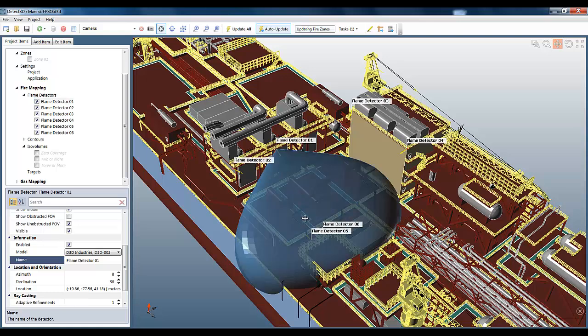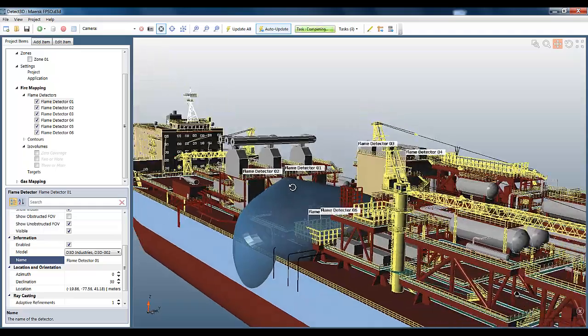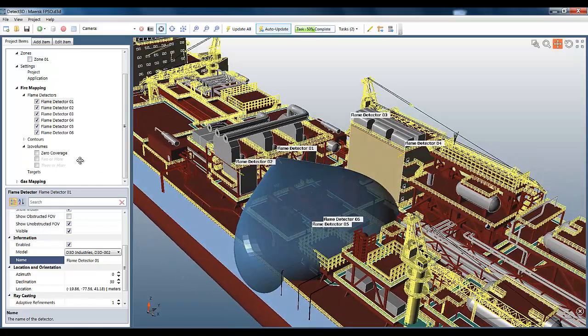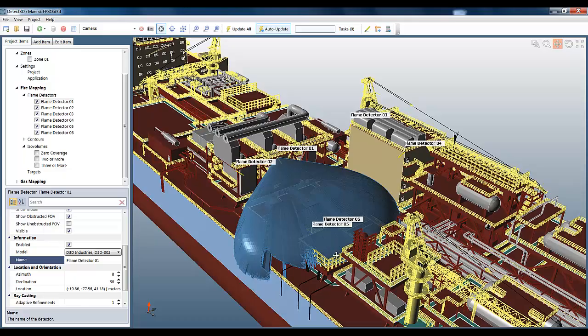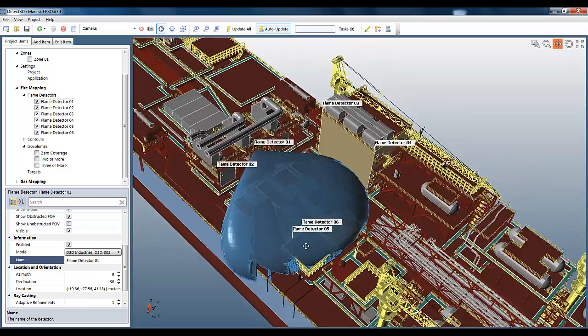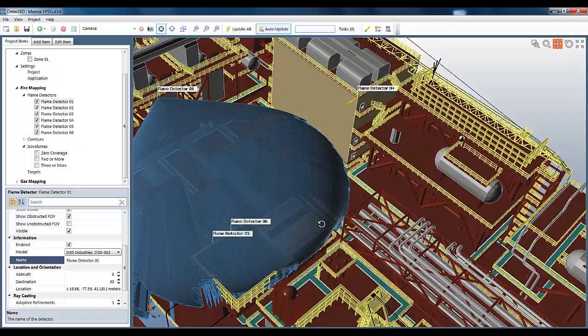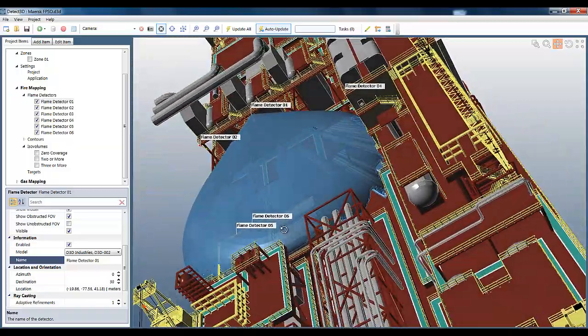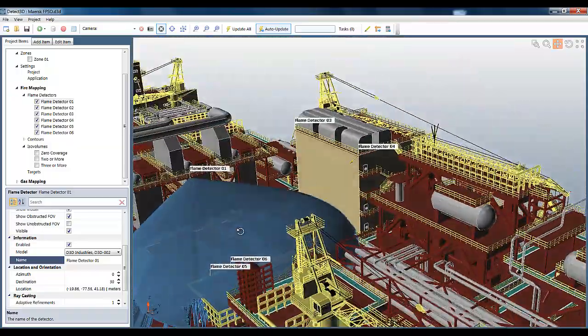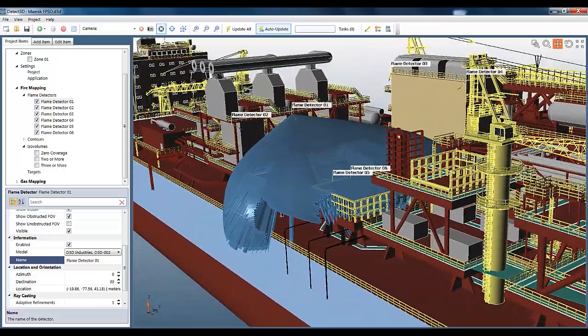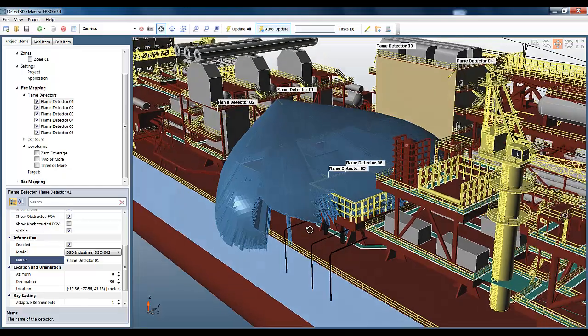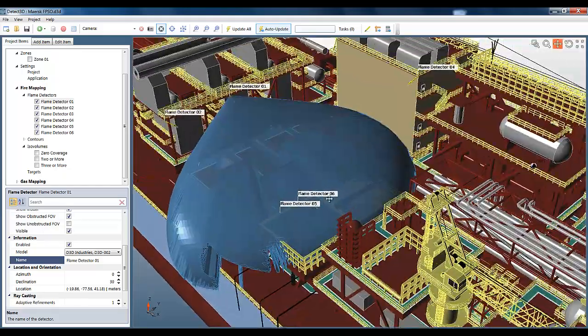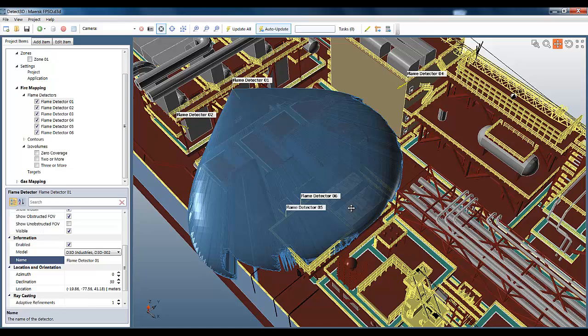And you should see the unobstructed field of view change to the more unusual looking one that I just created. Okay, there we go. Definitely see the change there in the shape of the field of view. And we can, of course, just double check this by looking at the obstructed field of view, checking all the raycasting is correct. And this looks good. You can just see a few rays coming through the railings there. But generally, it looks correct, and it shows you that you can put weird and wacky looking flame detector models into Detect3D, and it will handle it just fine.